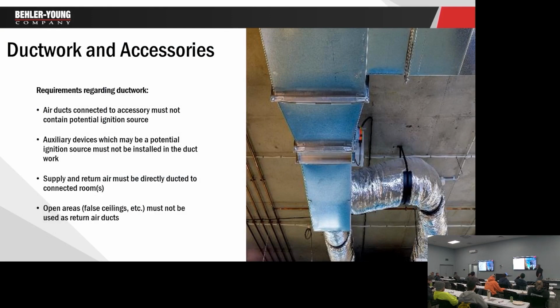So, some of the things we do know. We can't have any type of ignition source in our ductwork. If I add, say, an electronic air cleaner, I have to have an air switch on it. Heating elements: well, a heating element could be a heat source or an ignition source. Ours are not. If you look at the heating elements for the rooftop units, they are not ignition sources. They're rated so. However, what happens when we go to mitigate? If it detects a leak, it's going to shut the electric heat off anyway, right? Okay, so we can't put anything in there like that.